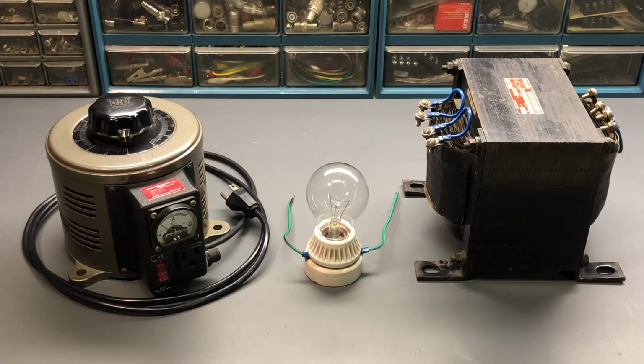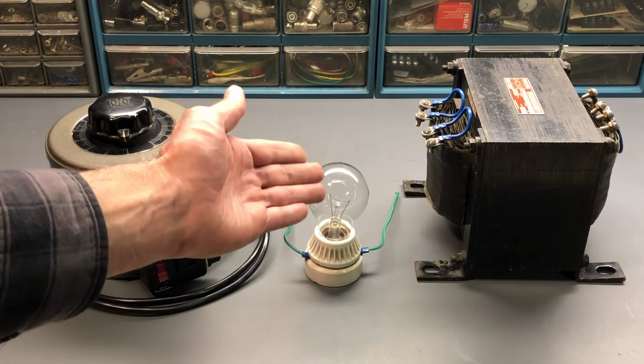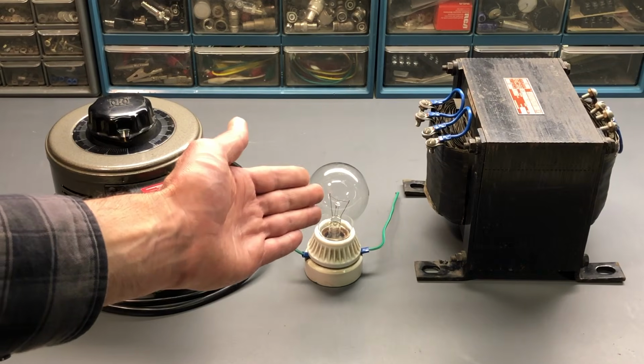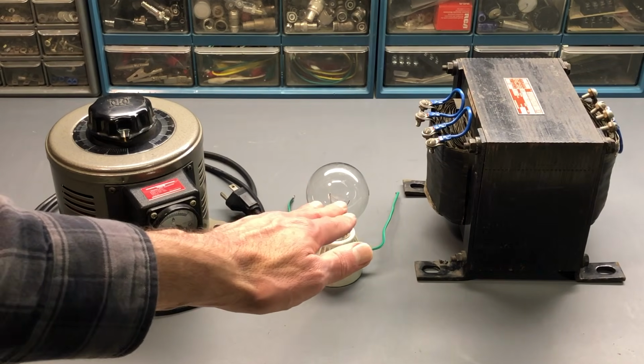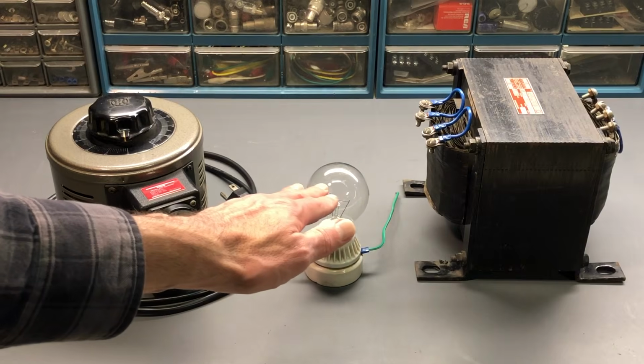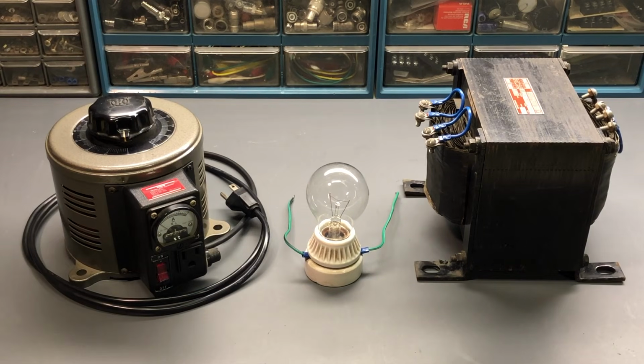Now, the term dim bulb comes into play because this bulb, in normal use, when it's in the circuit, will be glowing just very dim. You'll just have a slight glow across the bulb as a little bit of current is flowing through it, and that's what you typically want to see. If the bulb glows very, very bright, then you know that there is an excessive current draw, possibly even a short circuit on the device that you're testing. Or the bulb that you've selected is too low of a wattage.